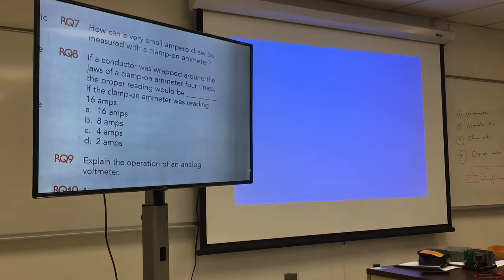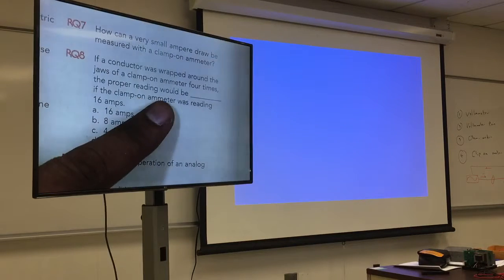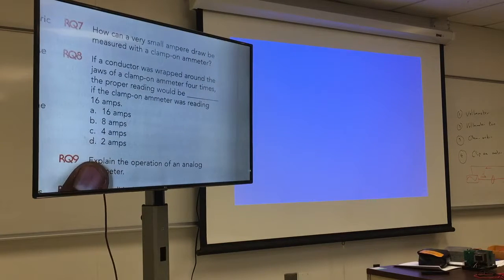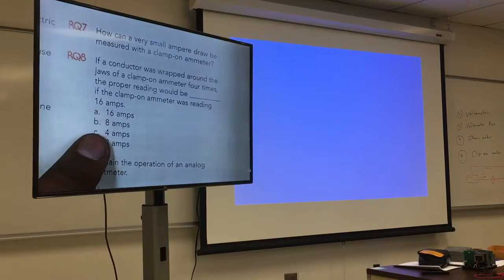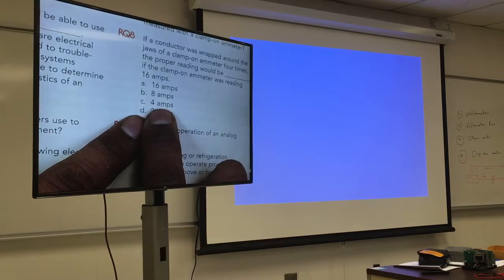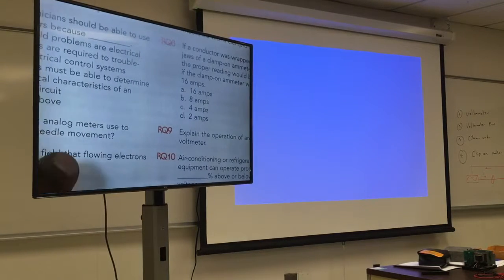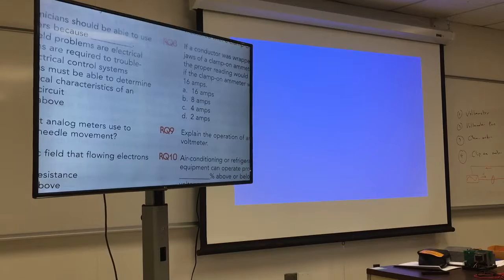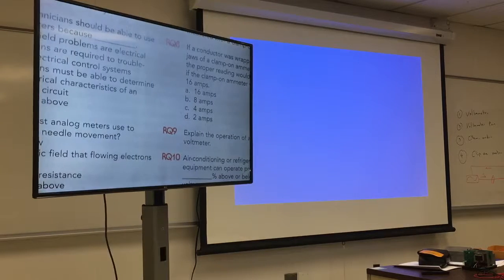If a conductor was wrapped around the jaws of a clamp-on meter 4 times, what would the proper reading be? If it was wrapped 4 times and you get 16 amps, then you divide by 4—by the number of loops, however many times you wrap it.